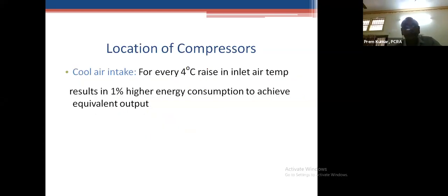So location is very important. For every 4 degrees, that is why we find the energy consumption during winter is low. November, December, January is low; April, May is higher. So try to cool the air. Later on, a case study is there, I'll show you. Cool the incoming air. This is the same for DG sets as well as for compressors. Every 4 degrees results in 1% more.